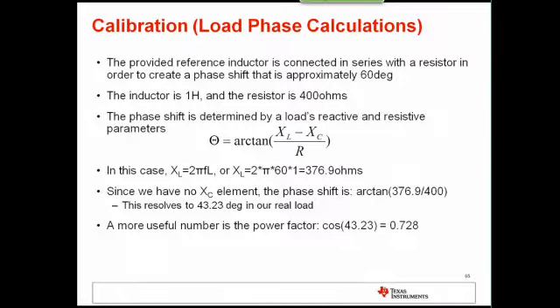So what we're going to do is calibrate our meters to a power factor of 0.728 using this. What that means is we're going to inject a known power factor, and then anything else outside of that is going to be due to the CT that we're using, so we can calibrate that out.